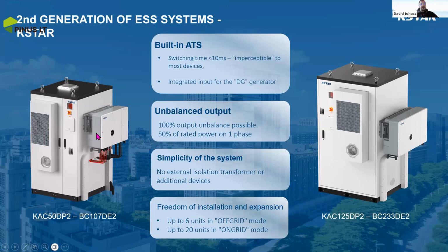There is no need to install an external isolation transformer on the load side, because it solves the smooth switchover from on-grid mode to off-grid mode. And the limitation is that we can use only 6 units in off-grid mode, and we can use 20 units in parallel in on-grid mode.